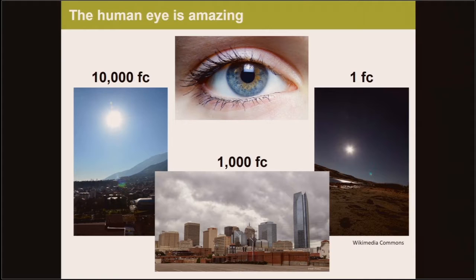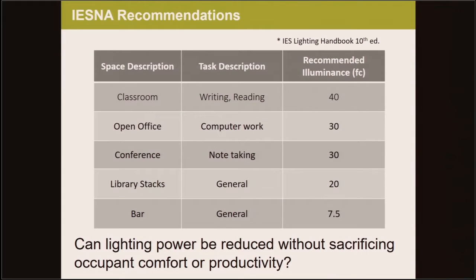It turns out our eyes are pretty amazing. They can quickly and dynamically adjust to clearly see in a wide range of environments, from sunny days at 10,000 foot candles, to cloudy days at about 1,000, to moonlit nights that have less than a foot candle. That's an order of magnitude adjustment of over 10,000 times. For commercial buildings, the Illuminating Engineering Society of North America publishes recommended amounts of light, called illuminance in foot candles, by space type and more directly by visual task. The more visually intense the task, the higher the recommended light level. Classrooms where you need to read and write require 40 foot candles, and bars where you don't need to do anything particularly visually intense require only 7.5 foot candles.